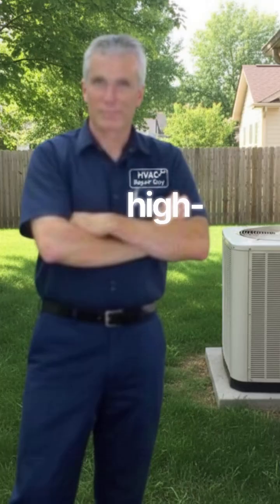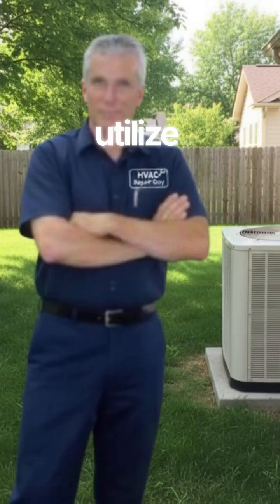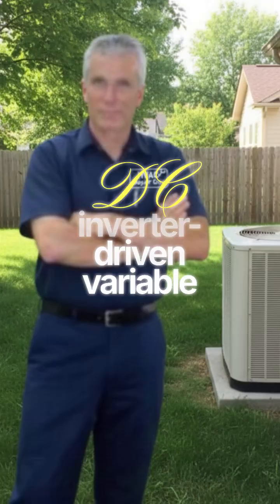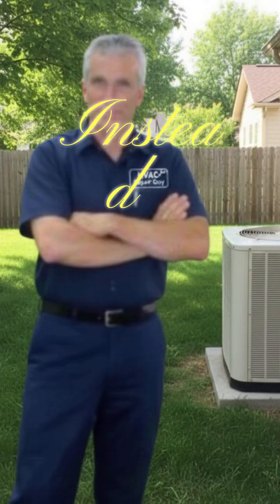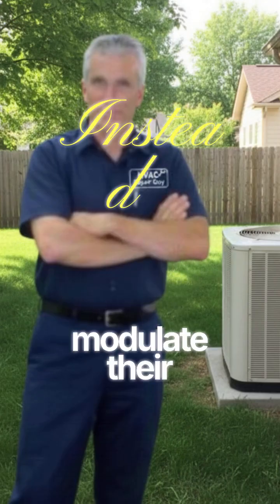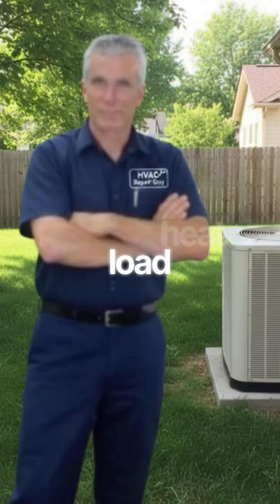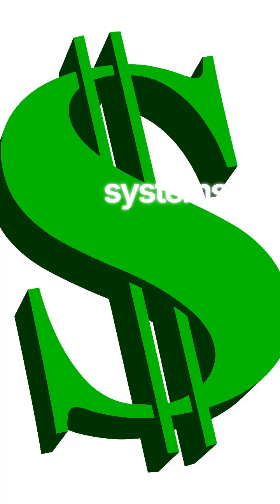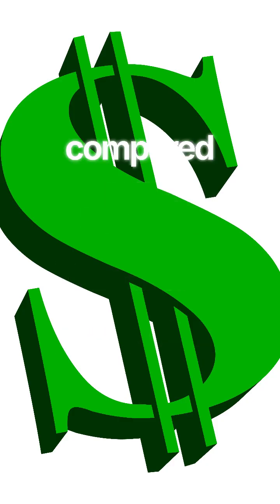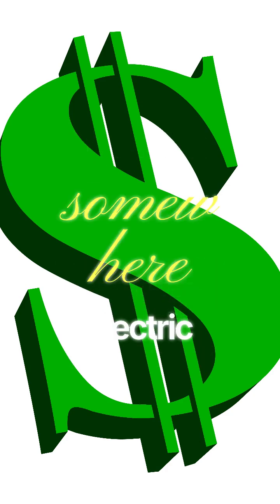Since these are high SEER units, they both utilize DC inverter-driven variable speed compressors. Instead of slamming on and off, they modulate their speed to match your room's heat load exactly. These are the systems that pay for themselves over time compared to a standard 14 or 16 SEER unit, especially if you live somewhere with high electric rates.